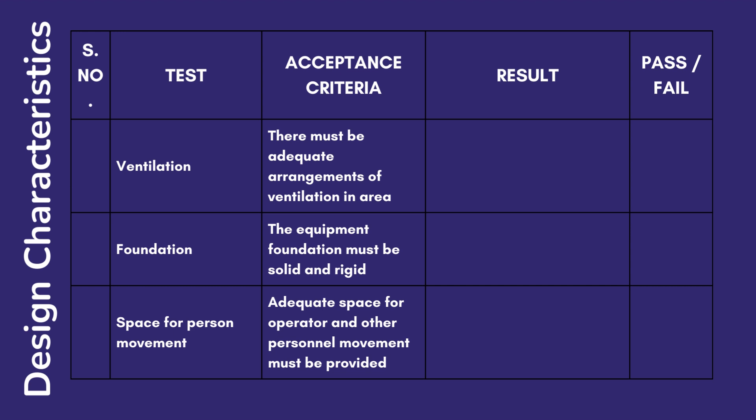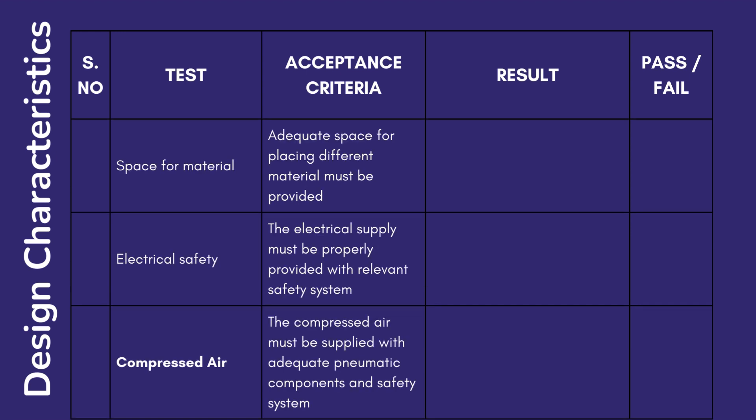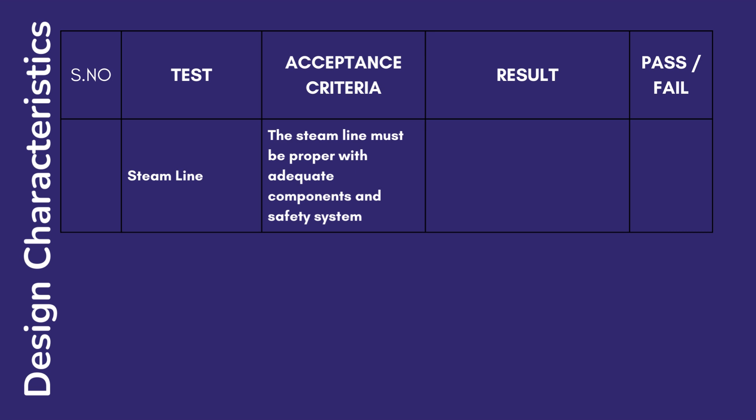Continued design considerations: Space for personal movement — adequate space for operator and other personnel movement must be provided. Space for material — adequate space for placing different materials must be provided. Electrical safety — the electrical supply must be properly provided with relevant safety systems. Compressed air — the compressed air must be supplied with adequate pneumatic components and safety systems. Steam line — the steam line must be properly installed with adequate components and safety systems.